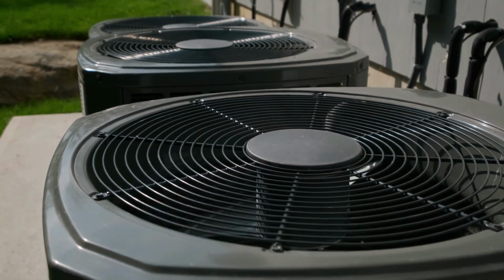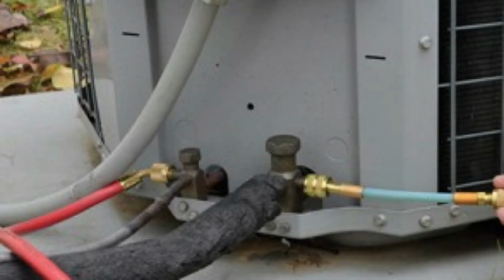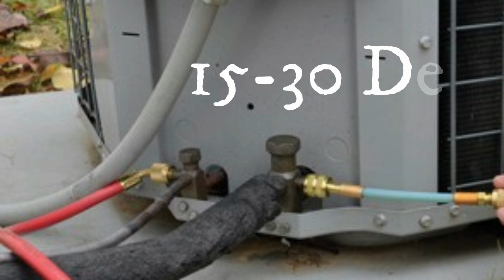Now the next two measurements we're going to take are outside on the outdoor unit. What we're going to do is take a temperature of our suction and our liquid copper lines going into the unit. Now this is a surface temperature reading, so you want to make sure you're using a device that reads surface temperature. Now what we're looking for here is very simple. We're looking for a temperature difference between these two lines anywhere between 15 and 30 degrees Fahrenheit. Anything more than that or less than that can indicate there's a problem in the refrigeration cycle somewhere. It could be a problem with the compressor, a TXV, a plugged line somewhere, or a kinked line set.